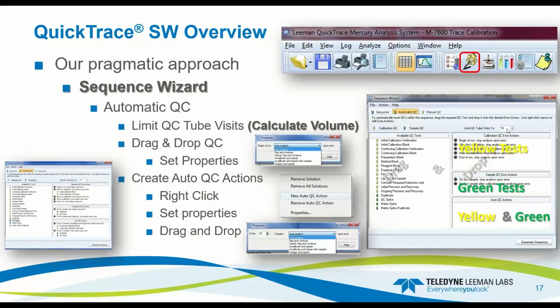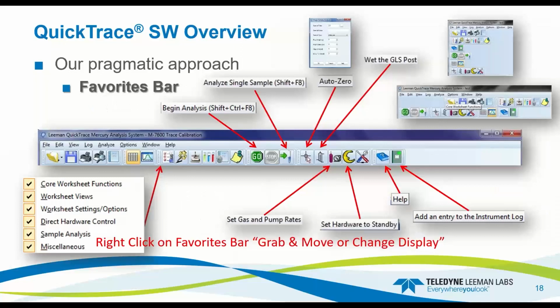So if I said I'm limiting it to 2, because I know I can only go into that tube twice, it's going to automatically load additional quality control samples in a rack that you designated as quality control, so it can complete the whole run. So if it knows it needs 1 every 10 and you have 50 samples and you can only go in there twice, it's going to load up 2 more continuing calibration verification, blanks and spikes and whatever you want in there. So it's really a nice feature. And then everything's color coded, so you can take it right to the hood, do a printout, and load up your sample vials.